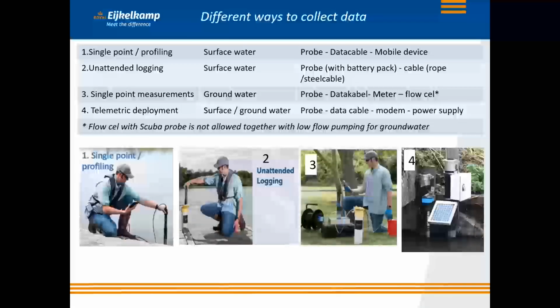In this table, I have summarized the 4 possible ways to collect the data: by single point profiling, unattended logging, so just put the probe in the water for some time and log all the data inside the probe, or active monitoring, single point measurements, and also telemetric deployment to collect data over time, weeks, days, or longer.